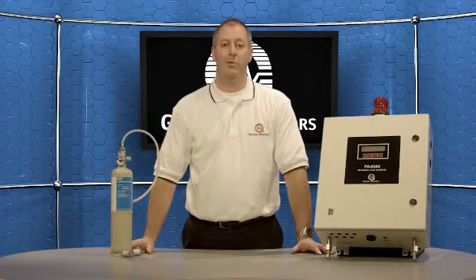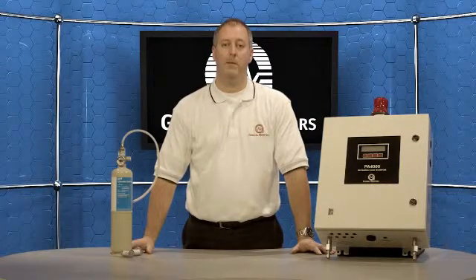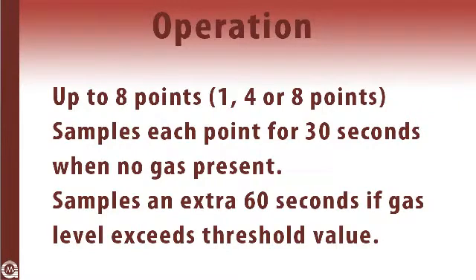So how does the sample get into the measuring cell? An internal pump and a set of valves pull a sample from up to 8 points that can be as far as 500 feet away from the monitor. The unit samples each point for 30 seconds when no target gas is present.